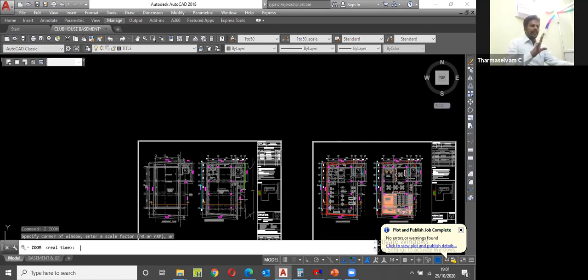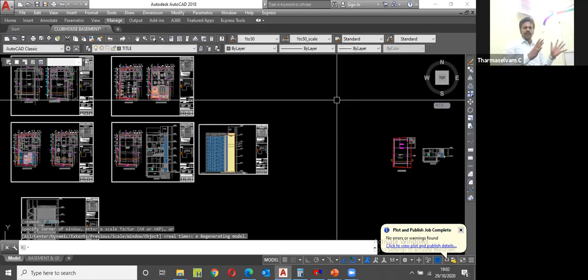First step, you go to study the diagram. At that time you segregate which are the ventilation and which rooms are under air conditioning. After that, you do the area summary. After completion of the area summary, you start the heat load calculation using your Excel sheet or HAP software. Once the heat load calculation is done, you select the equipment, whether it is an air handling unit or package AC, precision AC, rooftop unit, cassette AC, any kind of AC. Based on the application, you select. After that, you draw the diagram.